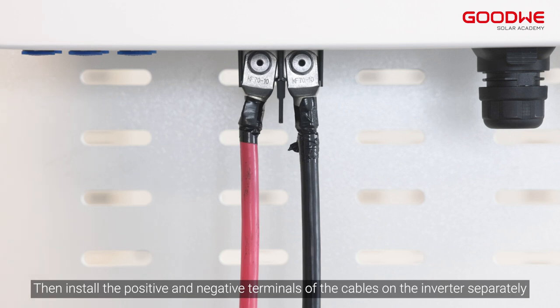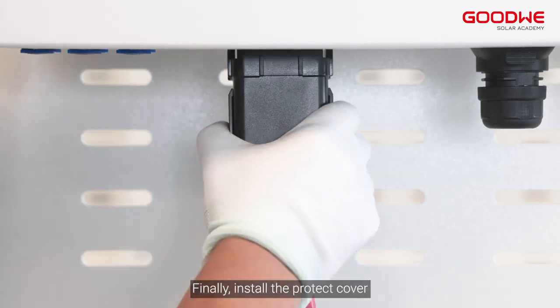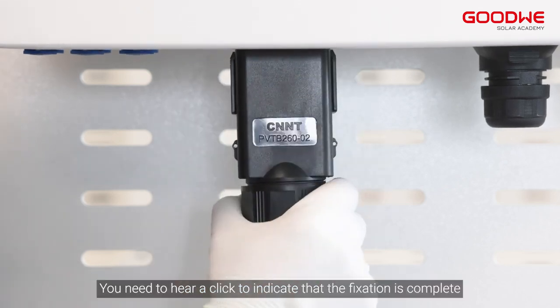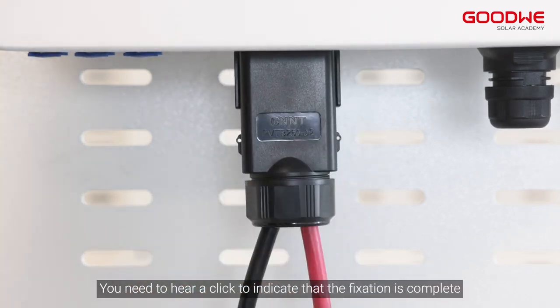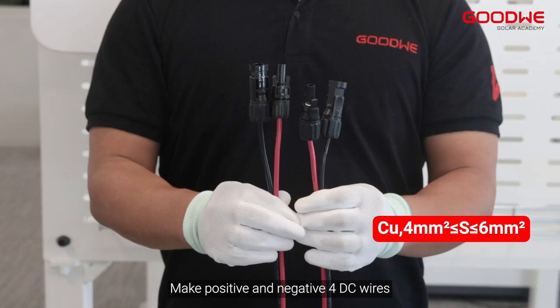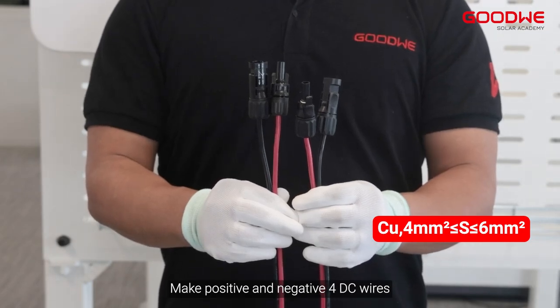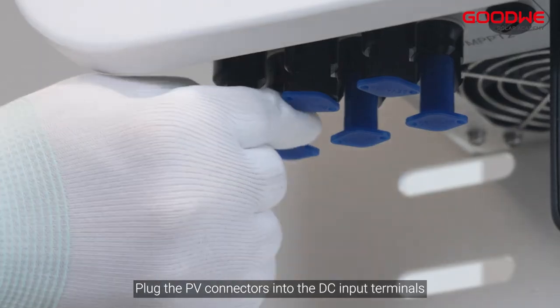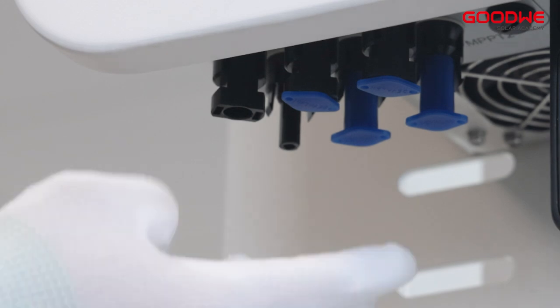Then install the positive and negative terminals of the cables on the inverter separately. Finally, install the protect cover. You need to hear a click to indicate that the fixation is complete. Make positive and negative 4 DC wires. Plug the PV connectors into the DC input terminals.